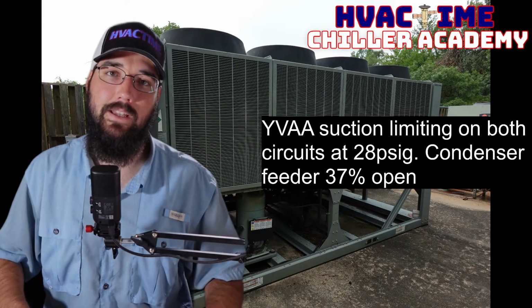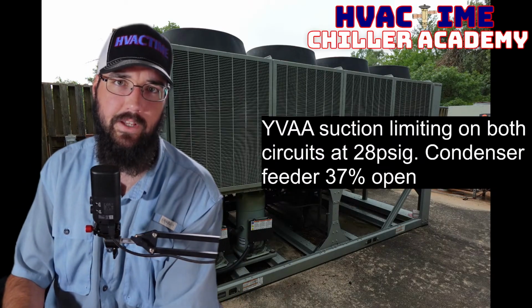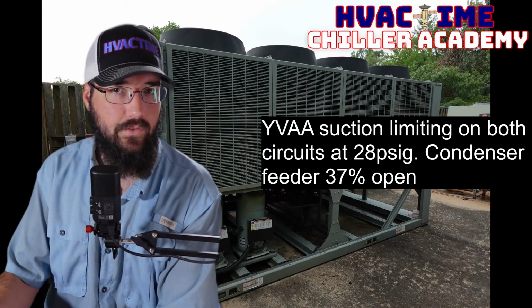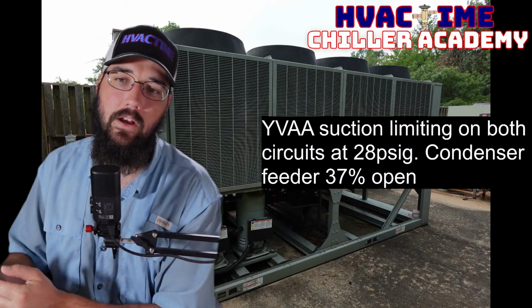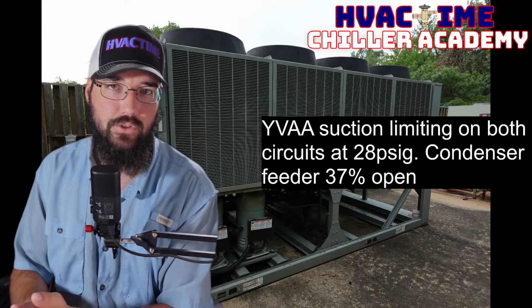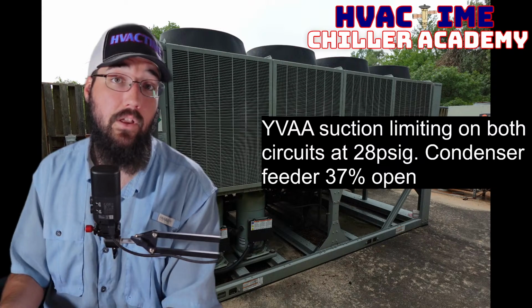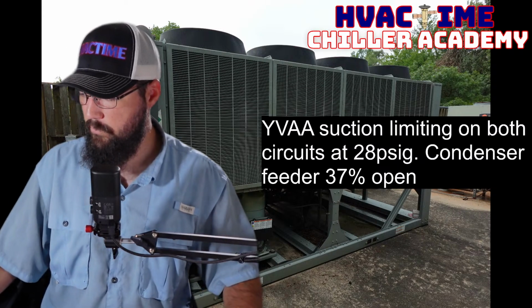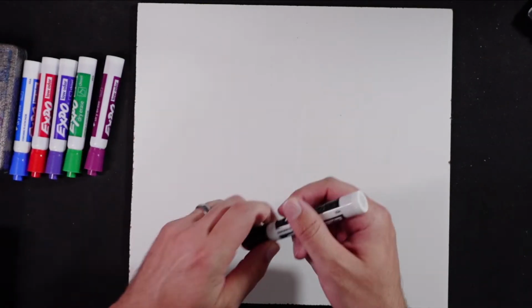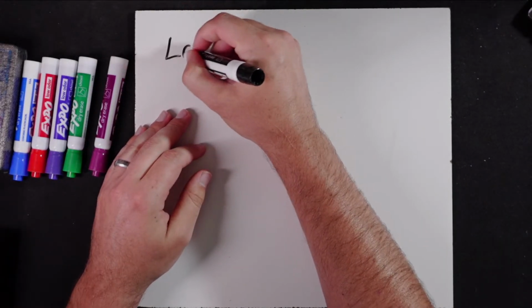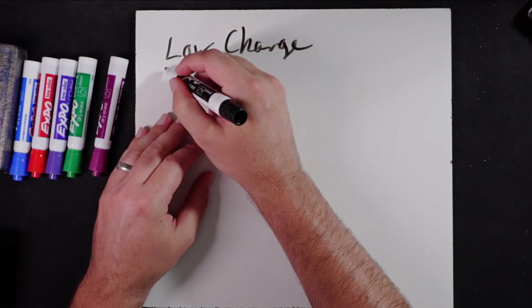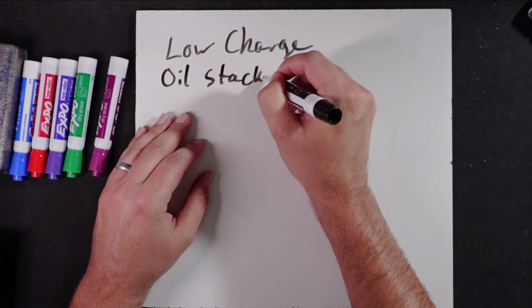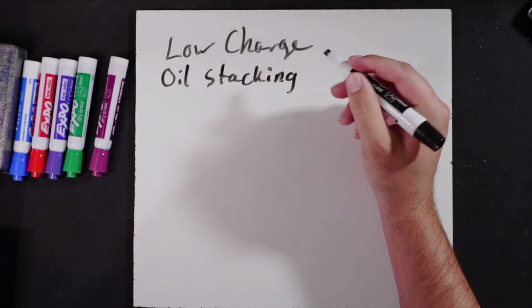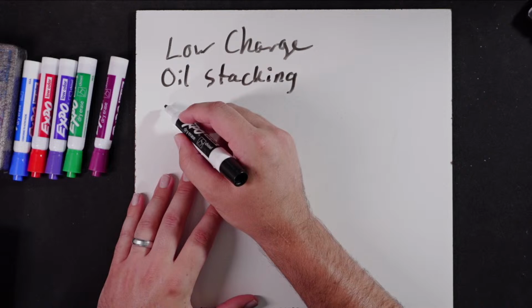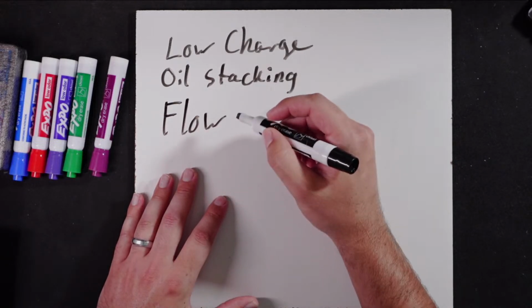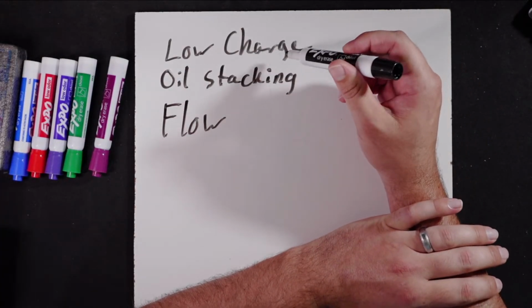I am actively rereading that just to make sure I've got all that straight in my mind. But that's my understanding. So if you had a low charge scenario, that could be a symptom of a suction limiting condition. Now, obviously with both circuits, I doubt that is true. So what is more likely is a flow issue. How about this? We could list out suction limiting potentials. So one would be low charge, which we talked about. We could have an oil stacking issue, which gets us into the eductor problems, or we could have a flow, which I think may be more likely, or heat exchange problem of some kind. So oil stacking is going to create a heat exchange problem as well as flow.